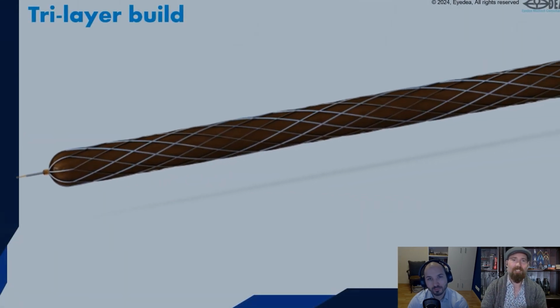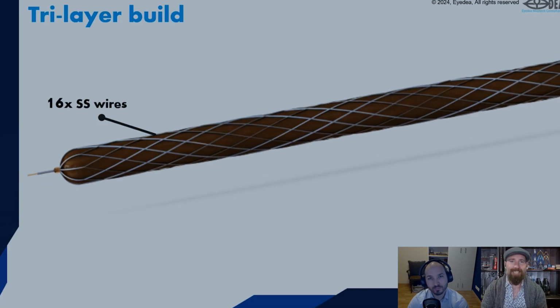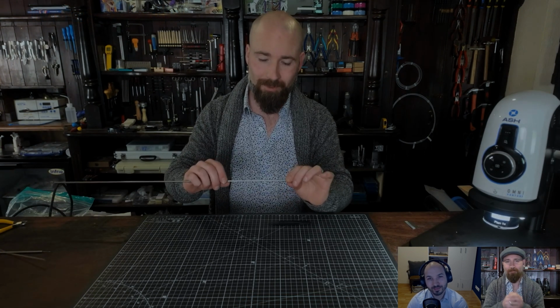Once you have it out the other end, you might need to cut and terminate that braid so that you're not cutting it at the very end and the wires open up and become really sharp points that go into the person. So you would think we have a very advanced, intelligent way of doing that. No, we do not. We put on a little bit of FEP heat shrink. This is just to hold the braid in place, and then we go in under a microscope with a snips and snip each one of those 16 wires, or 32 or 48 wires, and then we tuck them back in with the tweezers. Lovely job. Traumatizes people. I think after 6 months, people will actually walk out and leave a company if they're just left in this process.